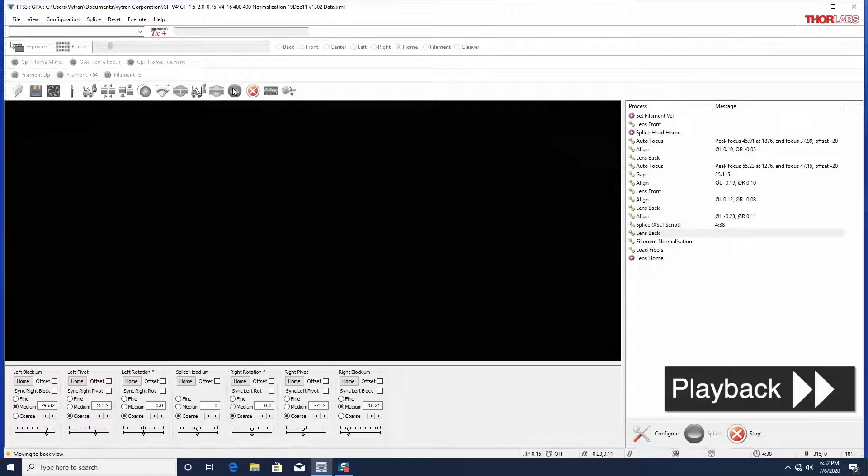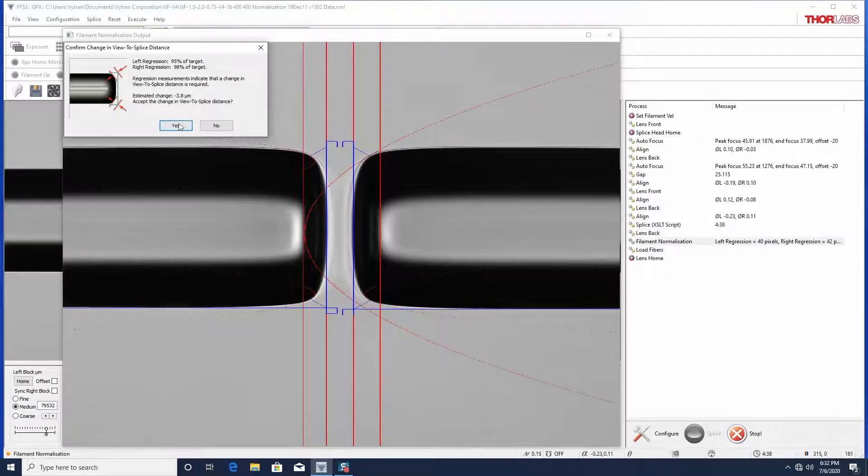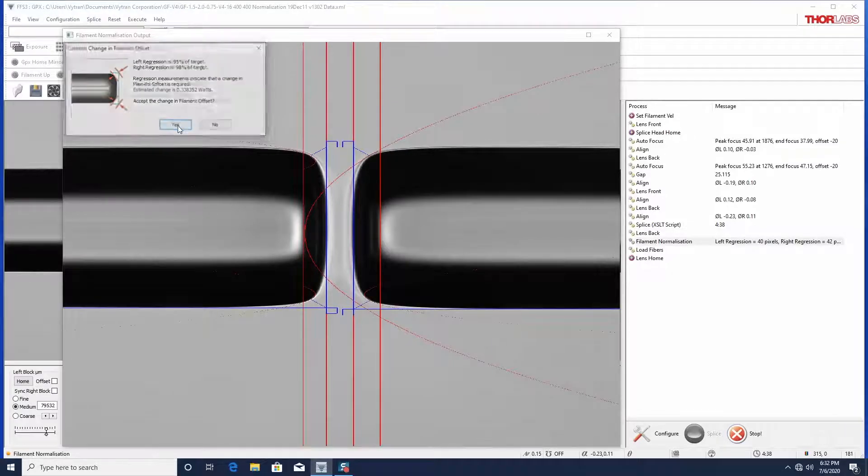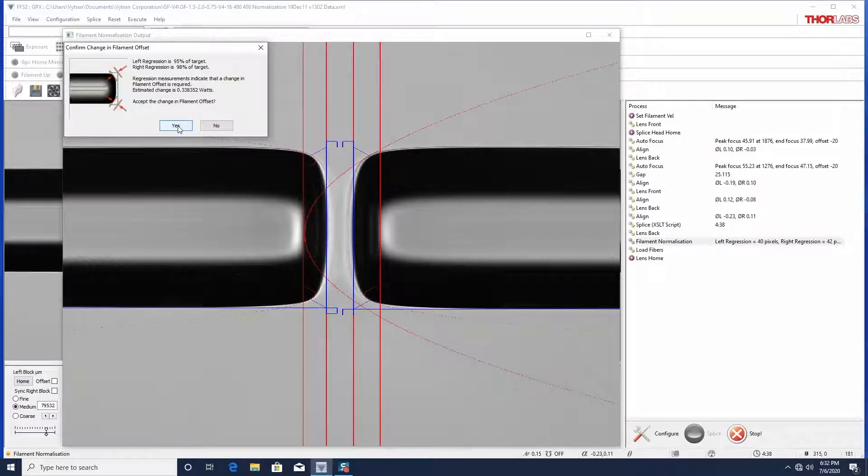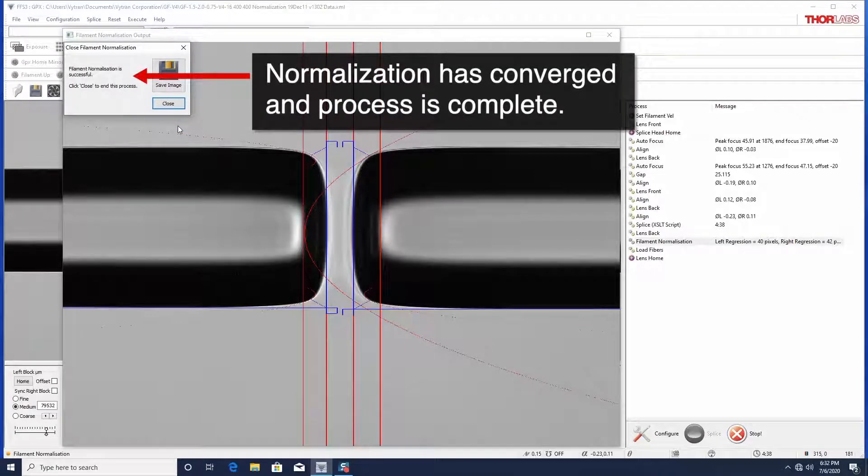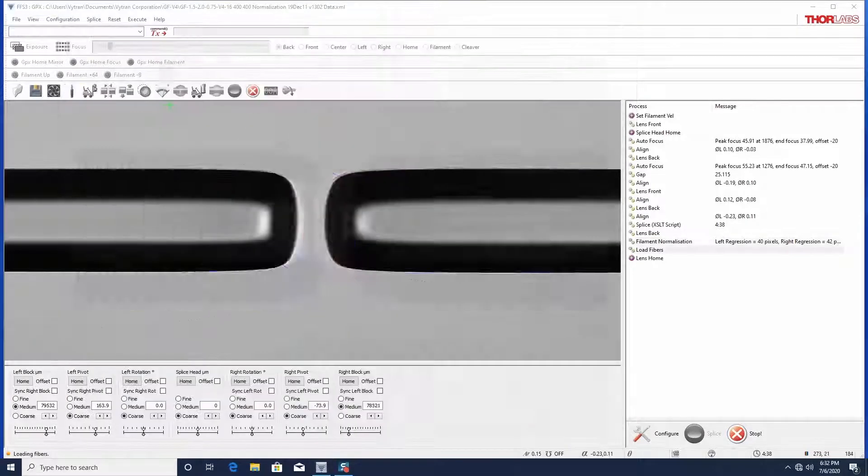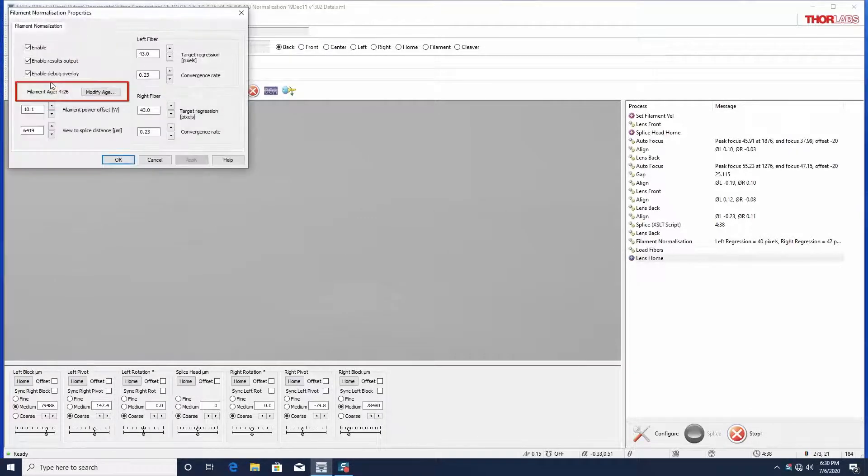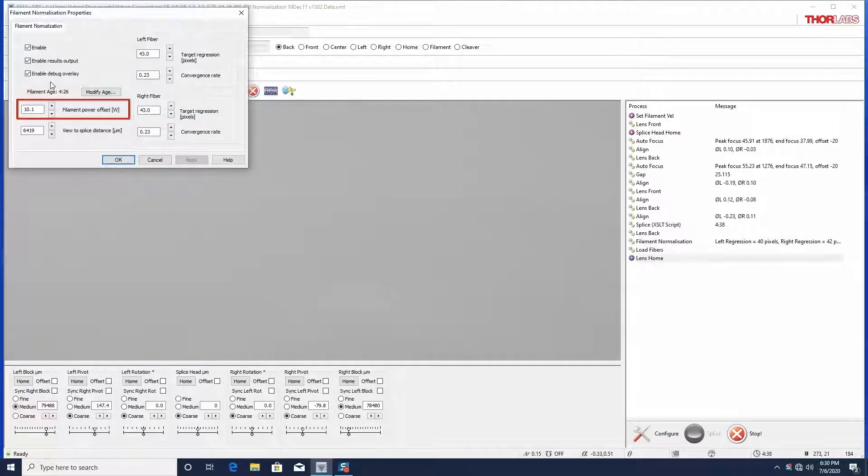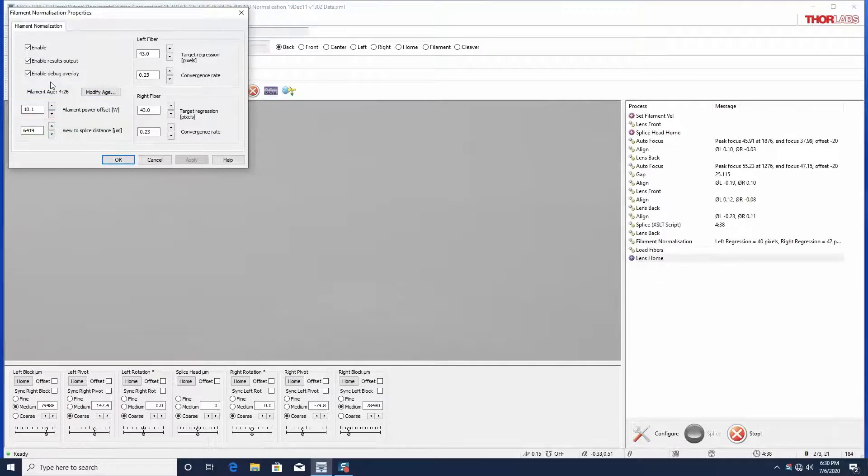It is good practice to keep a log of the filament power offset and view to splice distance set by the normalization process during the lifetime of a filament. If you remove a filament before its end of life, record the filament age, filament power offset, and view to splice distance. When you next install this filament, these parameters can be input as a starting point to expedite normalization, though it is typical for them to change.